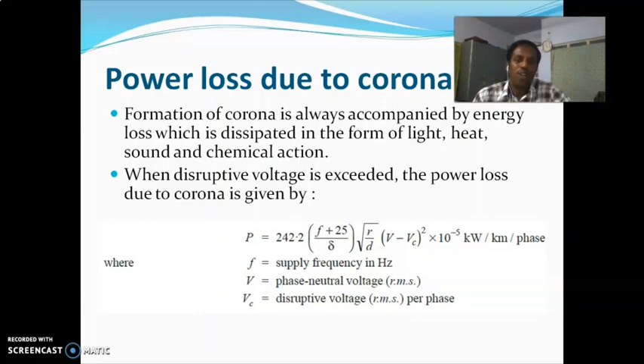And next one, what are all the advantages and disadvantages of corona? Corona is a disadvantage because power loss occurs due to the corona. So what are the advantages of corona? Due to the corona formation, the air surrounding the conductor becomes conducting and hence the virtual diameter of the conductor is increased. The increased diameter reduces the electrostatic stresses between the conductors. The potential gradient depends upon the voltage, distance and radius. Increasing the distance between the conductors will reduce the electrostatic stress, and increasing the radius or diameter of the conductor will also reduce the electrostatic stress.